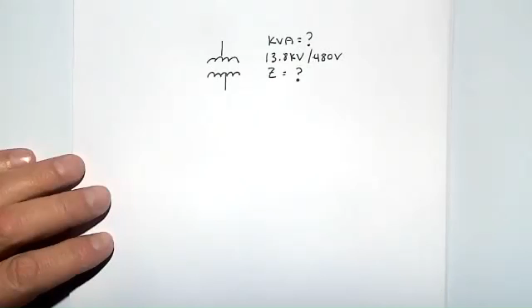So a lot of times we'll talk to the utility company, and let's say we determine that the kVA rating, either with some numbers written on the transformer, was 750 kVA, and we couldn't get a hold of the utility company, so what are we going to guess? Well, honestly, it's difficult to guess at transformer impedances, but in many cases, if we don't know the answer, a traditional impedance to use is 5.75%. I will tell you, though, that depending on the size of the transformer, this is not a great number for much larger transformers. And again, we mentioned for pole-mounted transformers it is not appropriate.